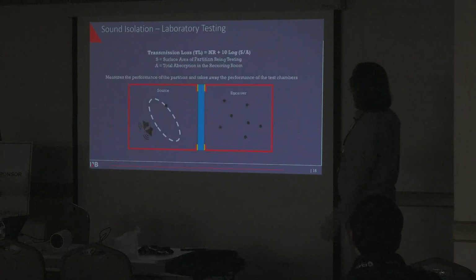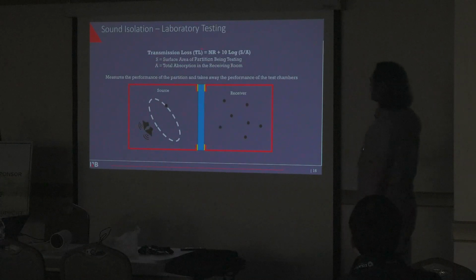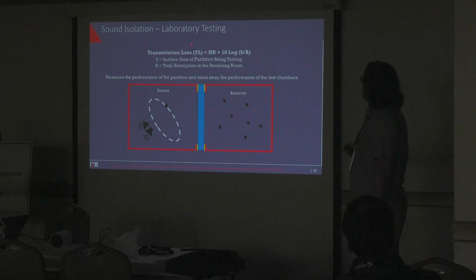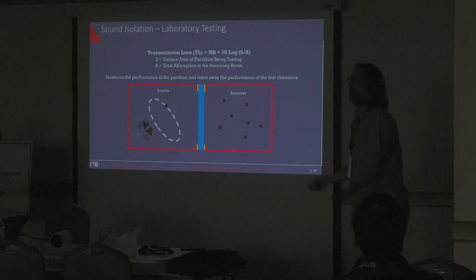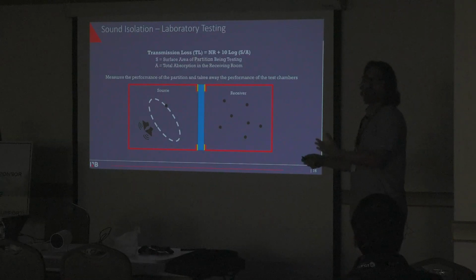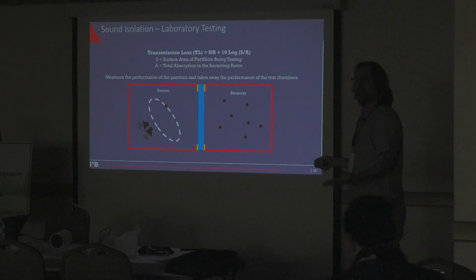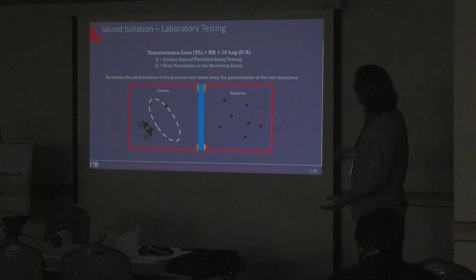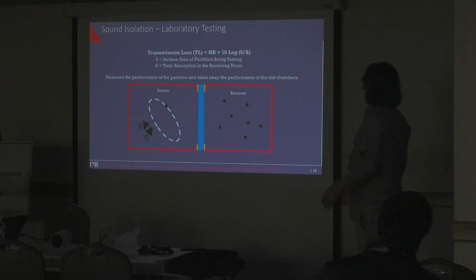That's not the final step, though. The final step is to turn those into a transmission loss, which accounts for the receiving room space. So we take our NR, and to account for the receiving room space, we take a 10 log of the surface area and the total absorption of the receiving room. What that basically does, in a nutshell, is take the receiving space out of the calculation, right? So if we had a concrete room versus a room that was carpeted everywhere, there'd be a different noise level in the space. We need to back that out so we know what just the wall itself does.